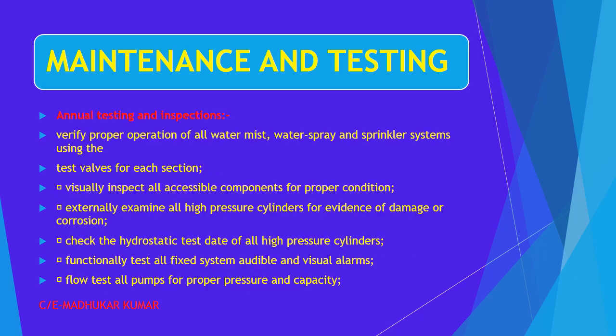Okay, so now the annual testing, monthly, what we have seen, it has to be continued. And annual testing, in addition to that, verify the proper operation of the water mist or water spray or the sprinkler system using the test valve for each section. That is again continued, and visually inspect all accessible components for proper condition. That means the visual inspection again continued over here.